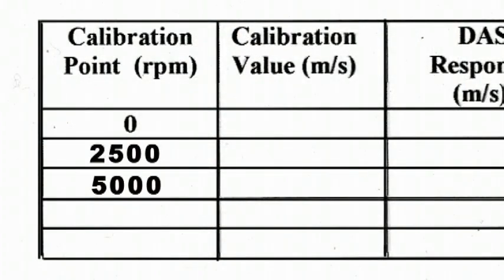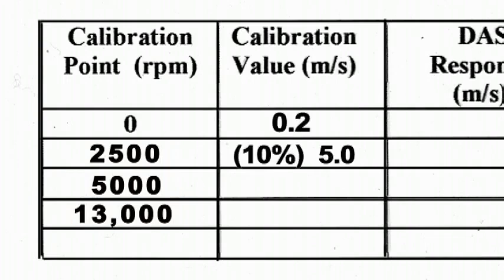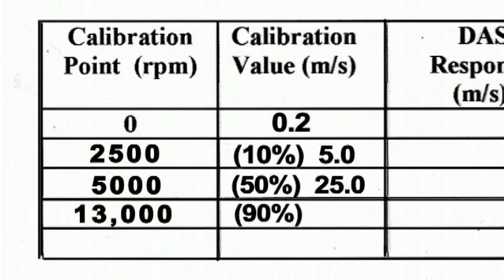At this time, we need to determine which RPMs will translate into the wind speeds. Reference your manufacturer's manual for the slope and intercept equation that translates the RPMs to wind speed. Using a calculator, enter in several RPMs into the slope-intercept equation to determine the source values at these RPMs. Generally, we would want a zero and three upscale points. I recommend points at 10%, 50%, and 90% of the full-scale range of the wind speed sensor. Enter these values into the table under the heading of the calibration values.